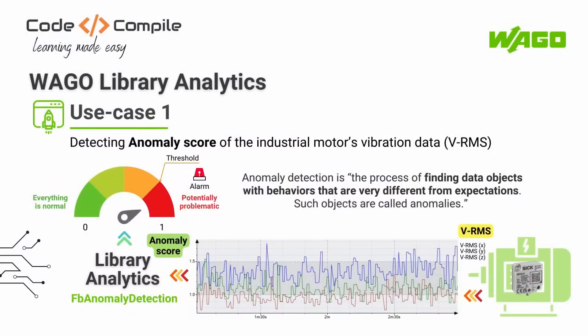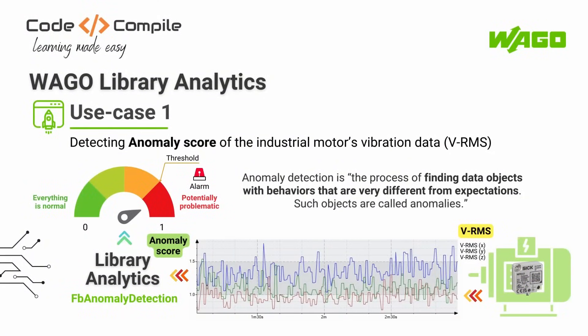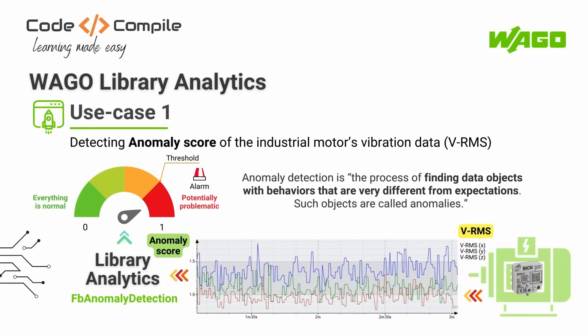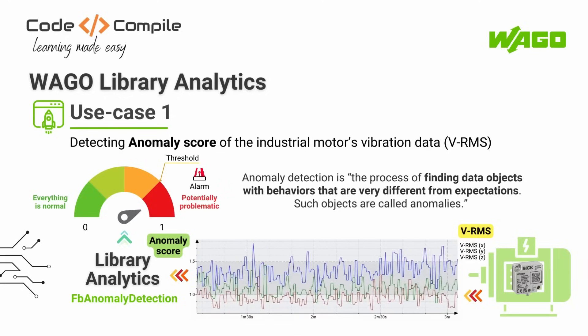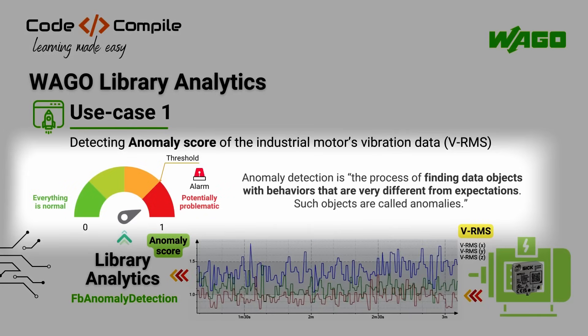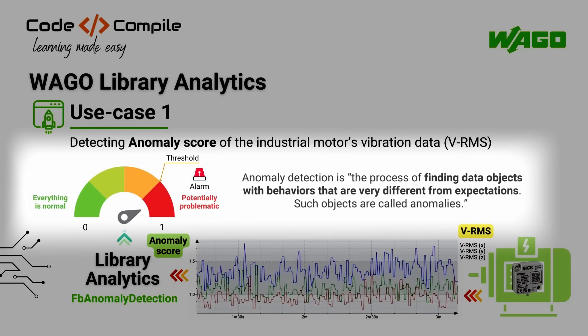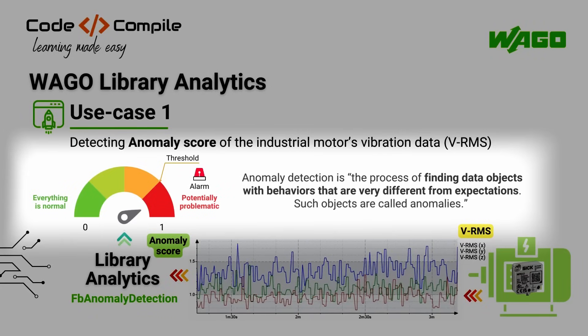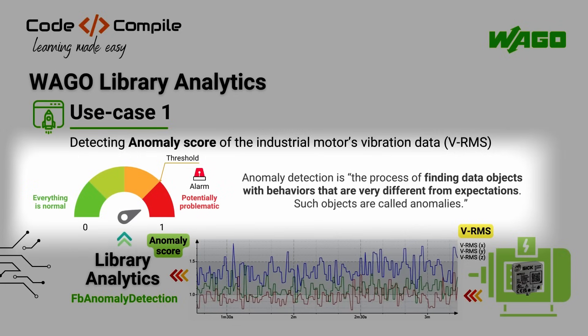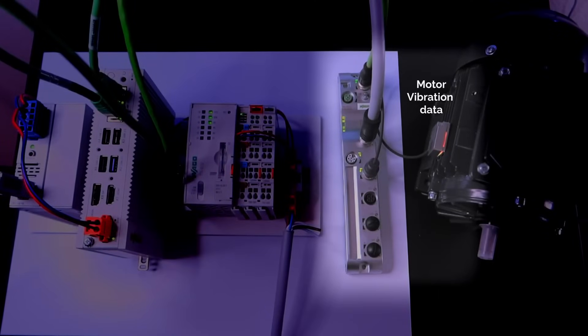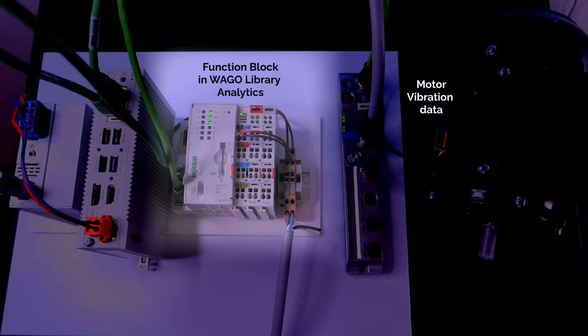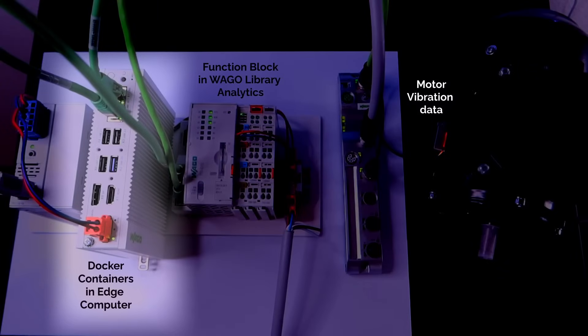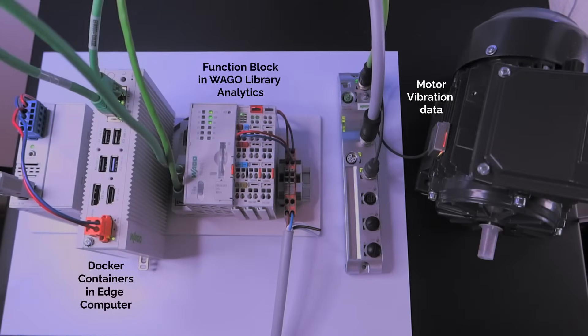So let's understand the first use case, which is detecting the anomaly score of a motor's vibration data. The anomaly score is a value between 0 and 1 that indicates behavior resulting from an unexpected and sudden change, where 1 represents the worst behavior and 0 represents the safest behavior. You just need to connect the motor vibration data to the function block of the anomaly detection, which will automatically send it to the specific Docker container to generate an anomaly score. And after defining the threshold, you can detect an incoming anomaly.